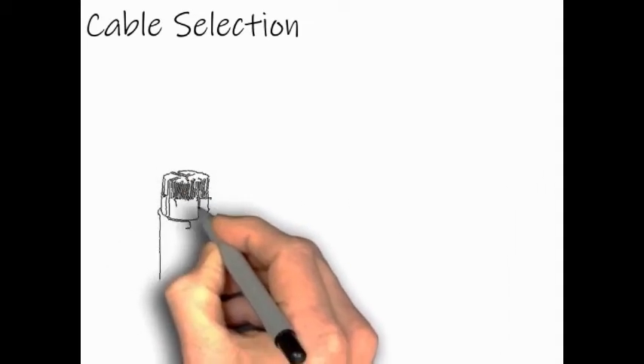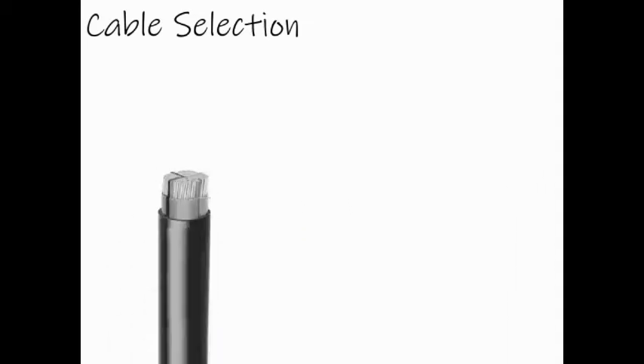The first factor that affects voltage drop is your selection of cables. The rated voltage of a cable is reference to how the cable is designed. The two key deciding factors on how cables are selected are the number of cores within the cable and also the cross-sectional area. For example, a multi-core PVC insulated shielded cable. In the illustration, the more conductors you have, the more current is able to flow.